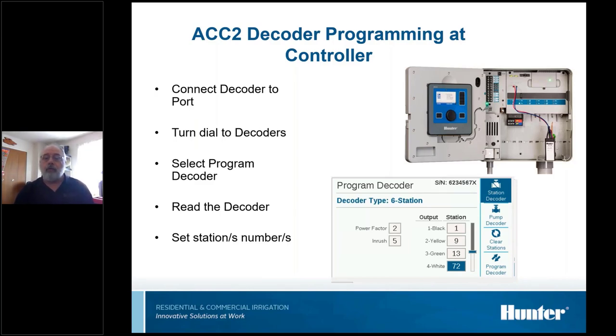You set the outputs to whatever station you want them to be. It does not have to be in numerical order. It doesn't care. We can leave blanks in any station number or output number we want. The one thing I will tell you is these two settings here, power factor and inrush. My best advice to you is do not touch these. Leave them at 2 and 5.